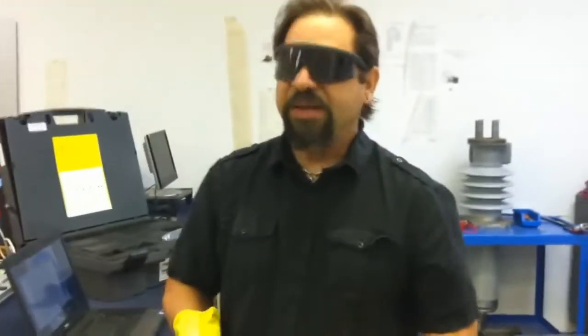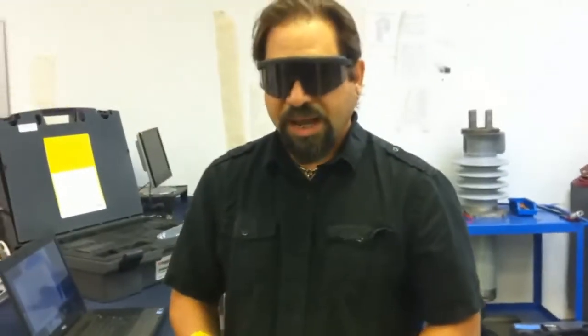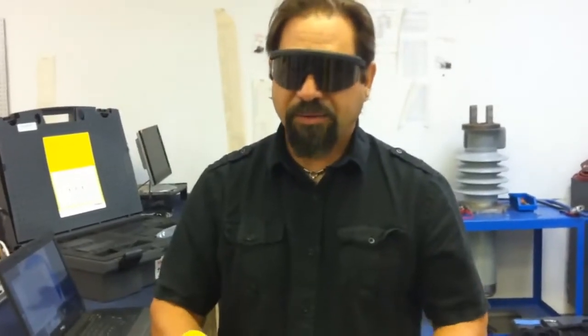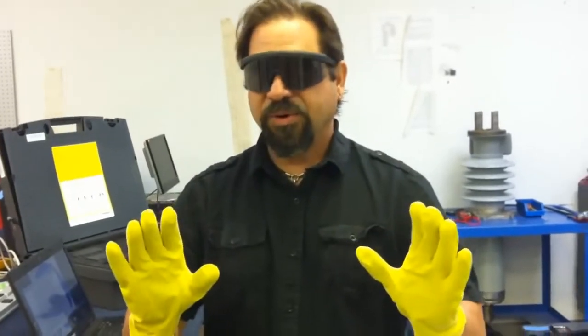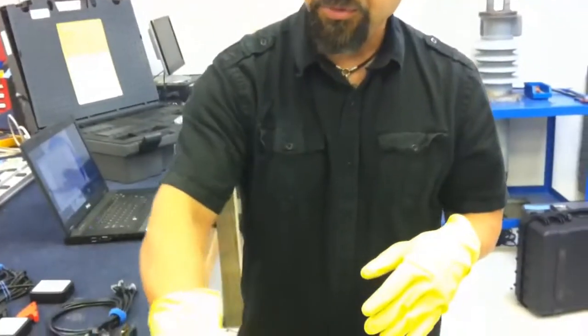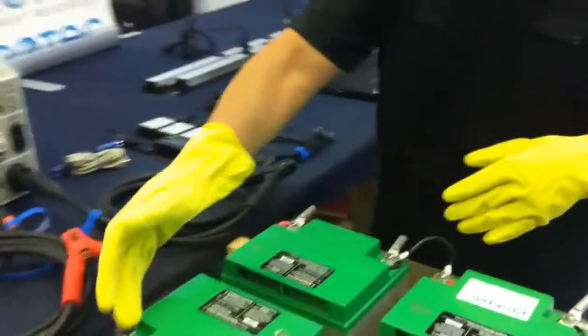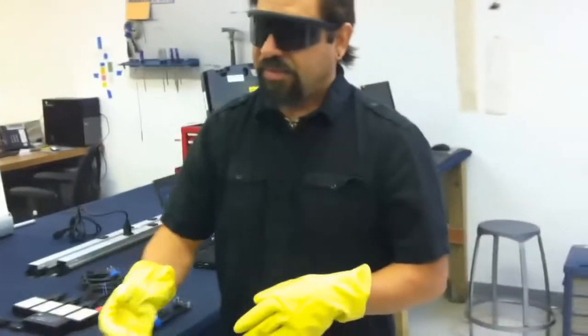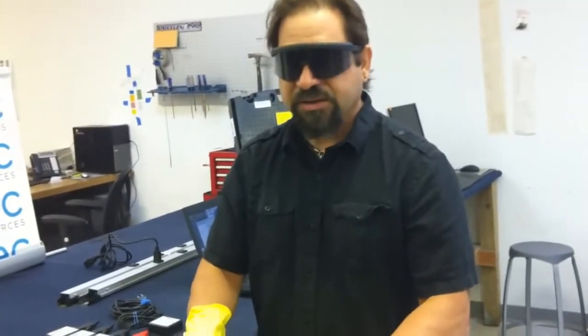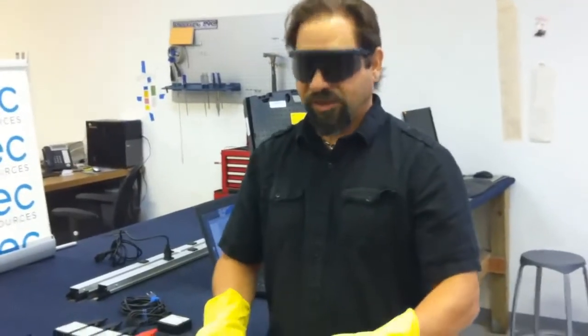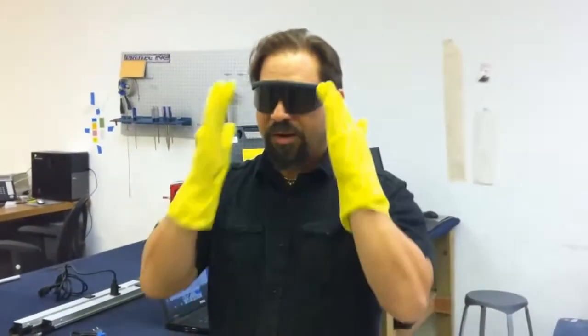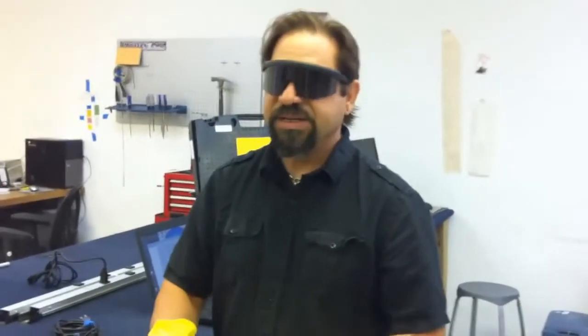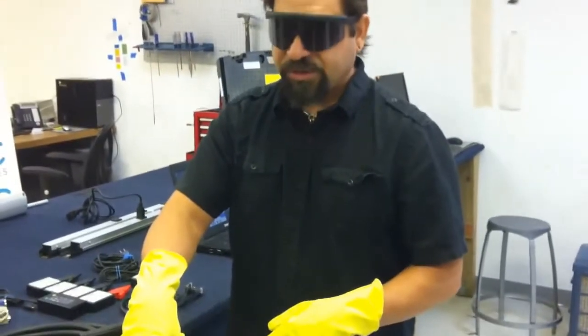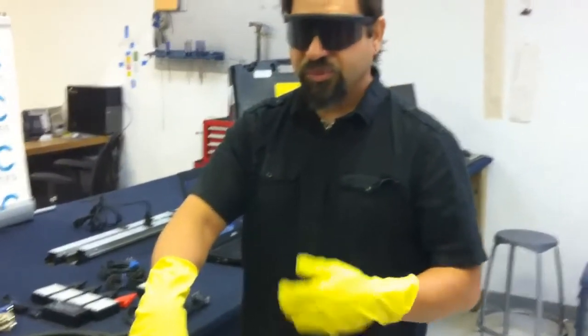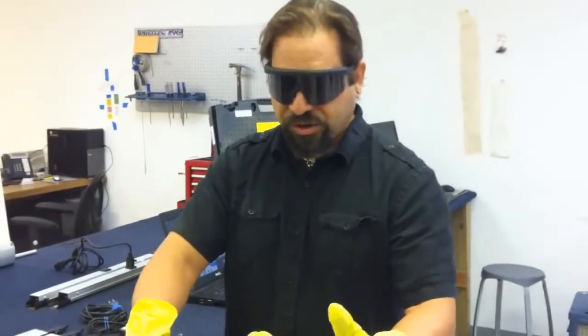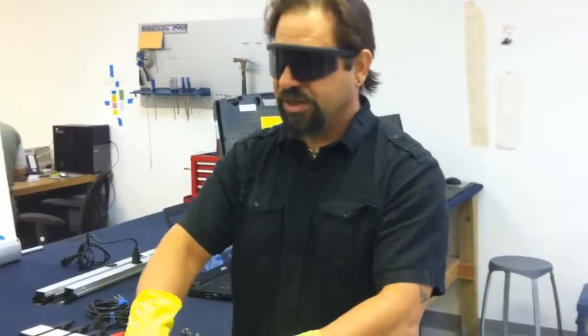Okay, you can see I put on some personal protection equipment. Whenever you're handling or working around batteries, you want to be wearing rubber gloves, even on sealed cells, because if you have any seepage or post-leakage, it will be corrosive and carry acid. If you are working around flooded cells, particularly doing hydrometer measurements, it's also highly recommended that you wear a rubber apron. Eye protection is important too—even in a sealed cell environment, if there are internal problems to these jars during the load test, it could cause a thermal runaway situation.